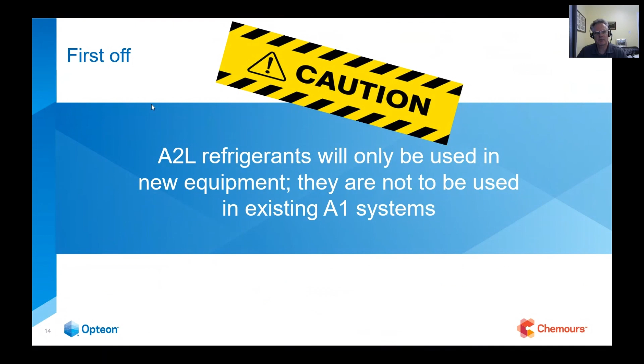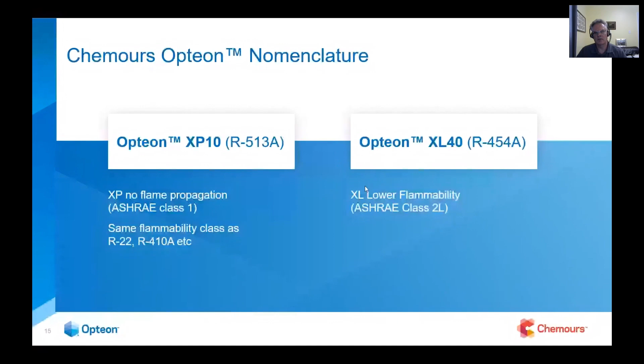So you cannot retrofit a 410A system to 32 or 454B, which are A2L class refrigerants. Next, from the ASHRAE numbers like 513A or 454A, you really can't tell what class a refrigerant is, you need to look at the ASHRAE Standard 34. But with our brand names, XP indicates it's in the same class as R22 in terms of flammability, no flame propagation, whereas XL in our designation shows that it is an A2L. Our competitors have done similar things with their nomenclature as well.